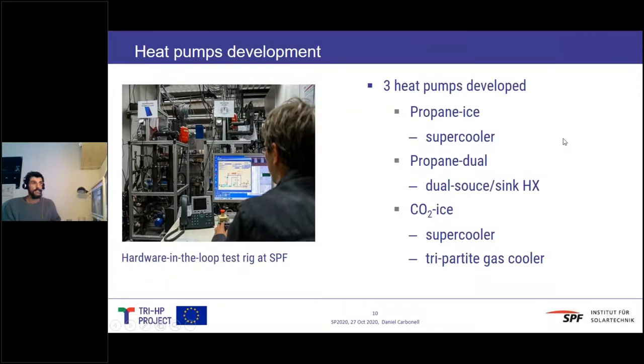All these heat exchangers are being implemented in three heat pumps. One is a propane ice with the supercooler, one is a propane dual with this dual-source/sink heat exchanger, and the last one is a CO2 ice using a supercooler and this tripartite gas cooler. Some of them are being tested now and others will be tested in the coming month.